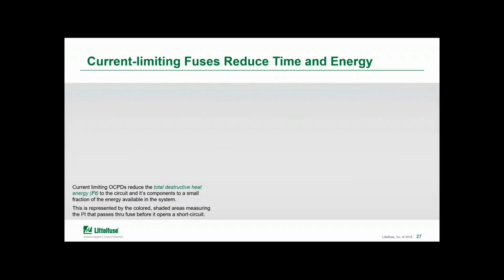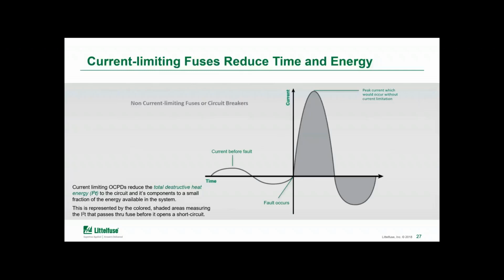As you saw, a current limiting overcurrent protective device can limit the destructive energy to a small fraction of what could normally flow in the circuit if it wasn't used. And so I think it's important to point out that there's a few differences between some of those current limiting devices and what time factor is associated with each. Now, UL specifically has the fuse classes RK5, RK1, J and T, and CC that are all considered to be current limiting fuses. However, there are some differences in the degree or levels of current limitation. So I want to make sure I outline current limiting as a definition.